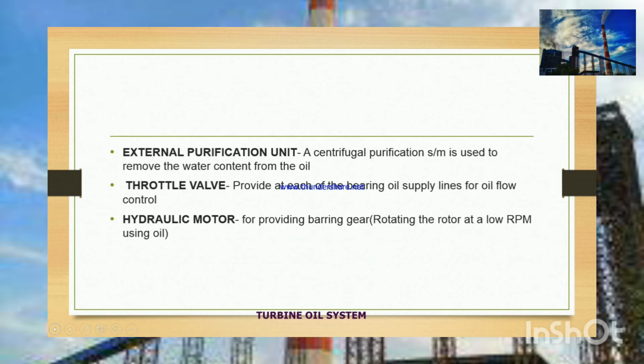Then third source is during the initial filling of MOT tank. During the filling, if we are using oil contaminated by water, then water will enter into turbine oil system. And the presence of water in oil will degrade the lubricating oil properties of the oil, and it will cause us corrosion.